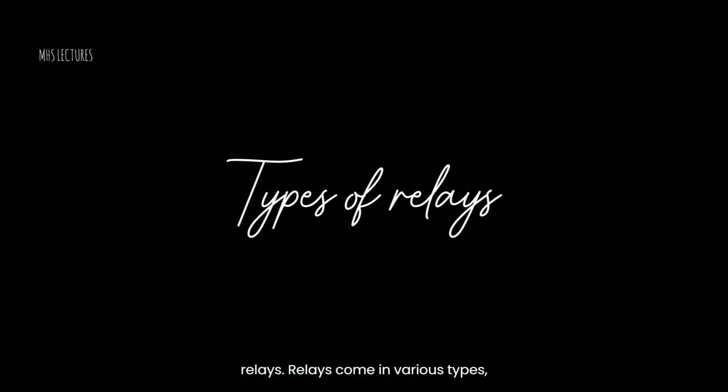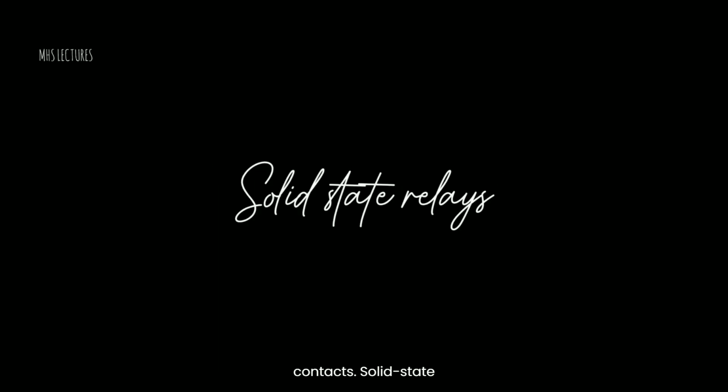3. Types of relays. Relays come in various types, each designed for specific applications. Some common types include electromechanical relays. These are the most basic type of relays, using mechanical movement to open or close contacts. Solid-state relays, SSRs. SSRs use semiconductor devices like transistors or thyristors to perform the switching operation. They offer faster response times and higher reliability than electromechanical relays.